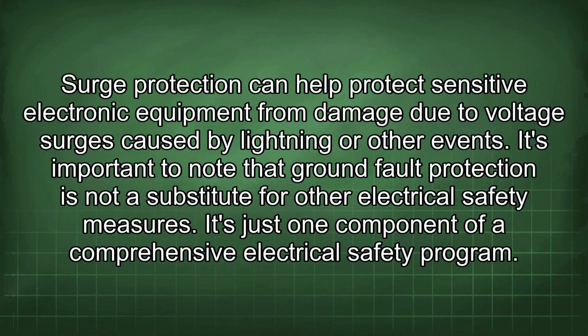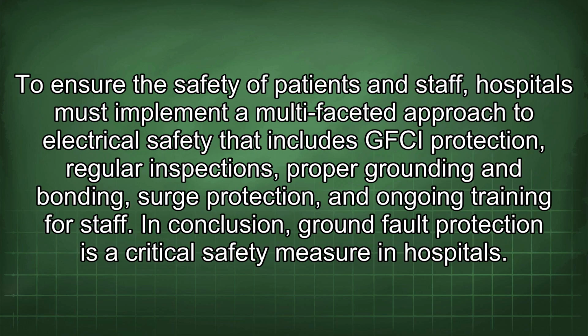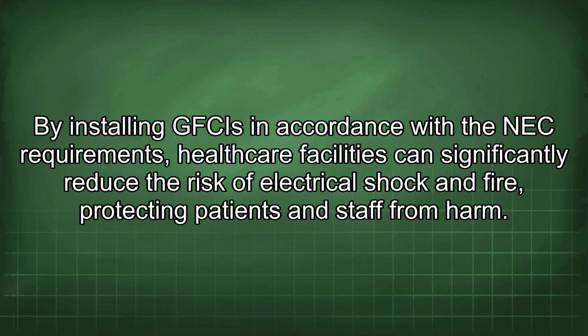It's important to note that ground fault protection is not a substitute for other electrical safety measures. It's just one component of a comprehensive electrical safety program. To ensure the safety of patients and staff, hospitals must implement a multifaceted approach to electrical safety that includes GFCI protection, regular inspections, proper grounding and bonding, surge protection, and ongoing training for staff. In conclusion, ground fault protection is a critical safety measure in hospitals. By installing GFCIs in accordance with the NEC requirements, healthcare facilities can significantly reduce the risk of electrical shock and fire, protecting patients and staff from harm.